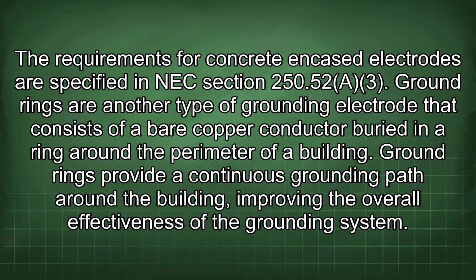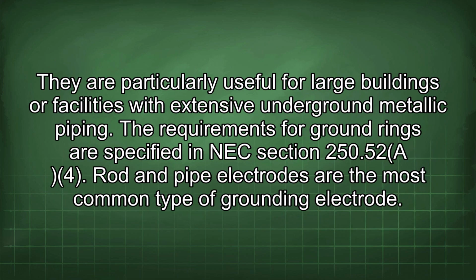Ground rings are another type of grounding electrode that consists of a bare copper conductor buried in a ring around the perimeter of a building. Ground rings provide a continuous grounding path around the building, improving the overall effectiveness of the grounding system. They are particularly useful for large buildings or facilities with extensive underground metallic piping. The requirements for ground rings are specified in NEC Section 250.52.